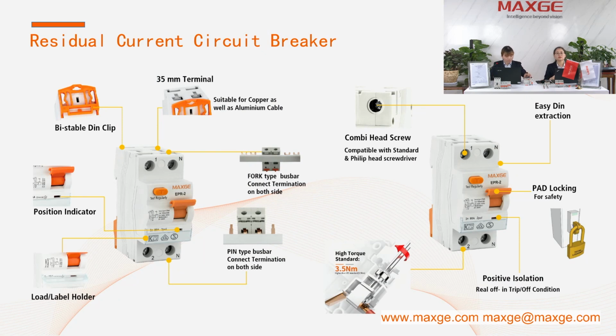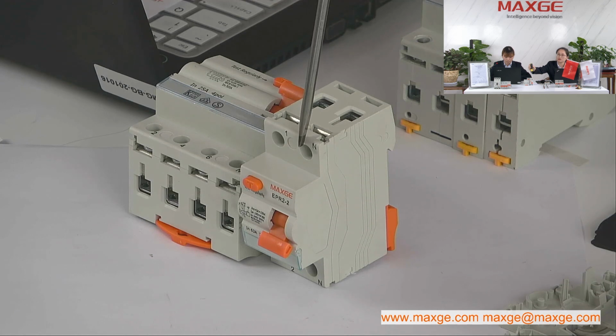Hello everyone, let me continue. Our RCCB comes with a combined screw drive head screw, which conforms to the standard and suits a Phillips head screwdriver. Electricians can easily choose tools during installation. It has a high torque of 3.5 Newton meters, while the IEC standard only requires 2.5 Newton meters.